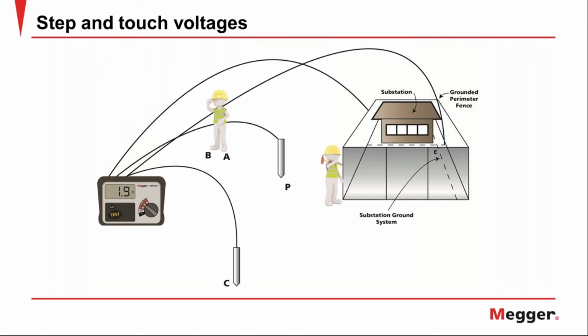So the way you do that, you take a 4-terminal tester, you make one current connection to the electrical grid, the grounding grid. You make your other current connection remotely. It's not real critical. That's C that you see there. That's just a probe that the operator drives in the ground some distance away. And then the potential probes, you're going to have one of them connected up to the fence, and the other one, your P probe, is in the ground about 3 feet away from the fence. So that's your touch potential.